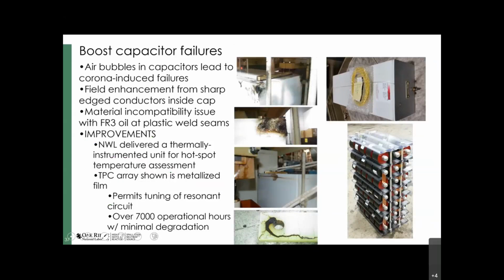A lot of the problems have to do with the fact that in our application, the electric fields internal to the capacitor are quite high because of the proximity to other non-equal potential surfaces throughout the machine. So we would get events where we would actually arc through the case, as shown here and here.